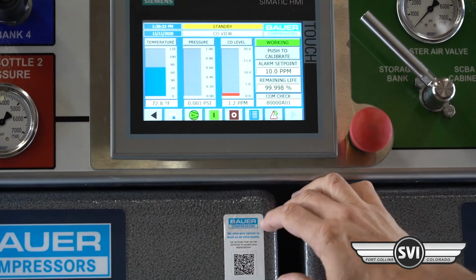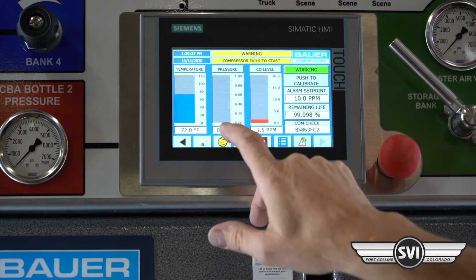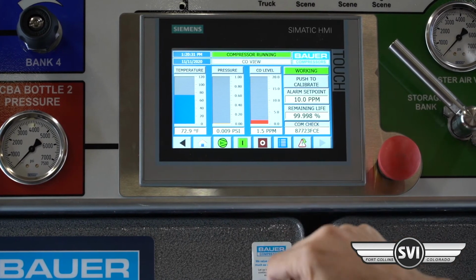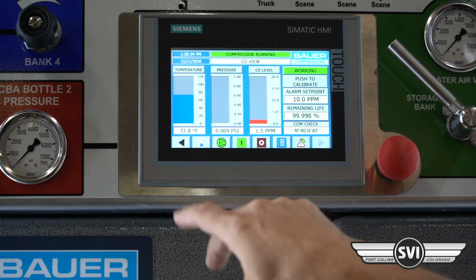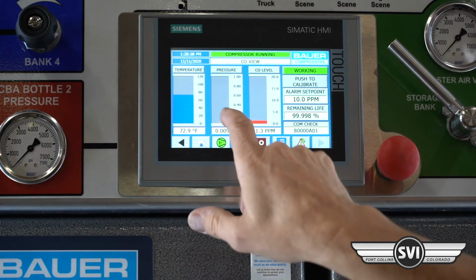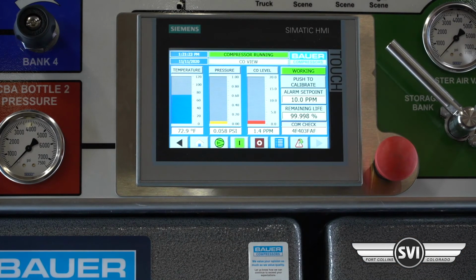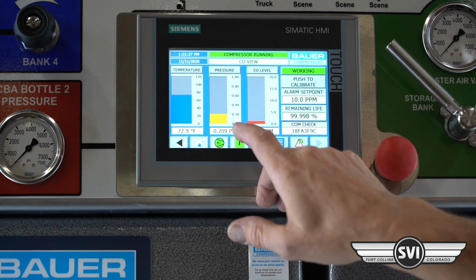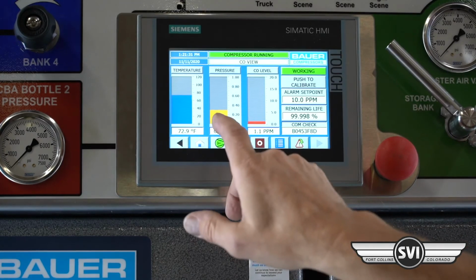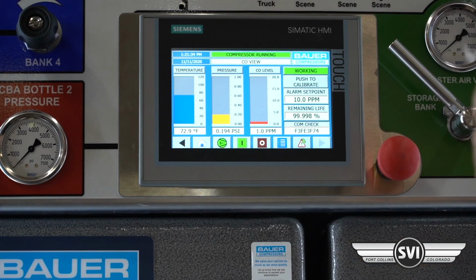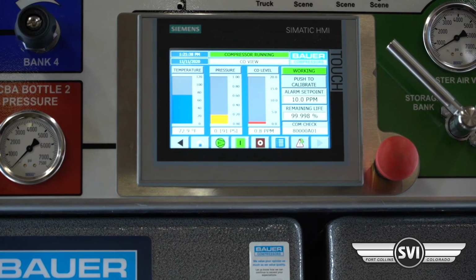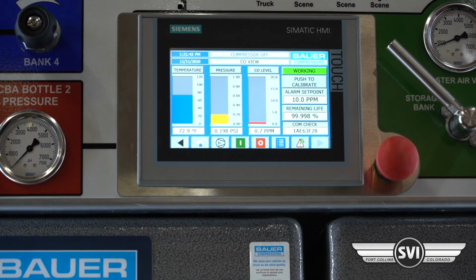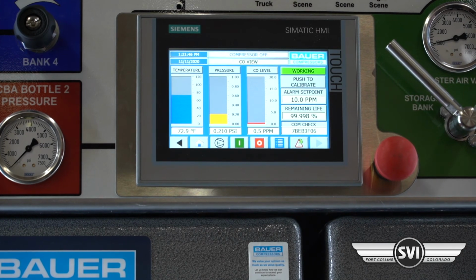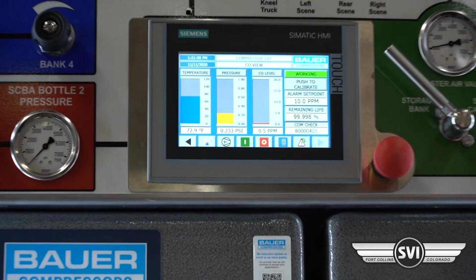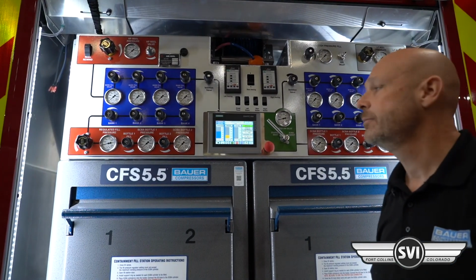So if we start the compressor, it'll start up, and we should start to see our pressure here. Once the pressure maintaining valve opens, it'll start supplying the sampling air. Now we're starting to get some pressure through the PMV, so we want to make sure that this is reading, and then the PPM will slowly purge out. Now it's functional, and we can shut the system off. At that point you'd record that you did a calibration or put a calibration sticker on it, whatever the procedure is. The CO monitor has now been calibrated and is functional.